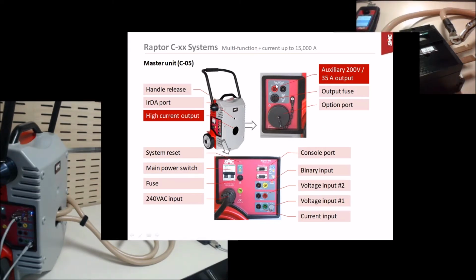It's useful for applications like, for example, determining the saturation voltage in a current transformer. Okay, this is what we use for that. And on the other side of the unit, you have a number of measurement inputs. For example, a voltage input here, an ammeter here, and extremely sensitive voltage input here for some millivolt sensitivity.